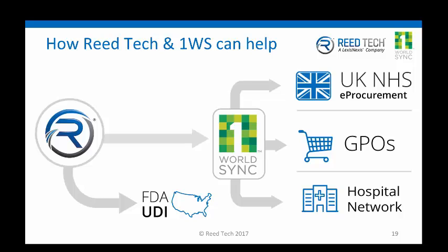But at a high level, the type of data that the FDA requires for UDI shouldn't change too much based on the Class 1 submissions. So depending on the size of your product inventory, I would advise that you prepare by identifying where this stuff is so you can start gathering it, perhaps maintaining it, prior to even having to submit it to the FDA, so you're not in a scramble when 2020 does come around.